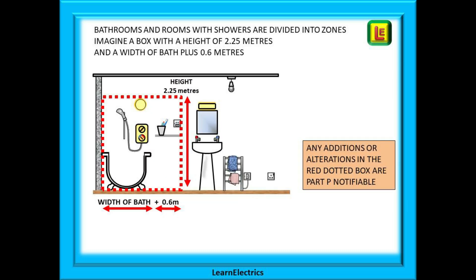Bathrooms and rooms with showers are divided into zones. Imagine a box that is 2.25 metres high and with a width that is the width of the bath plus 0.6 metres. If the bath was 0.68 metres in width, that would make our box 1.28 metres wide. Part P will apply to any alterations and additions that take place in this box measuring 2.25 metres high and 1.28 metres wide.